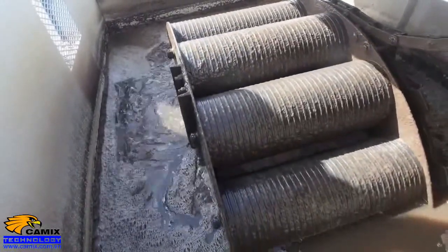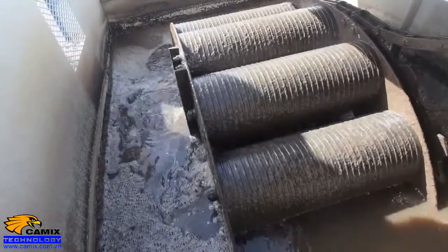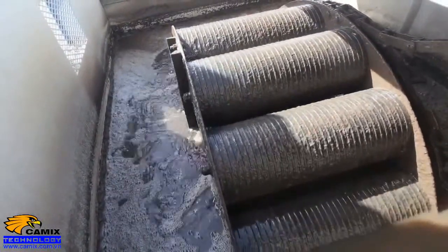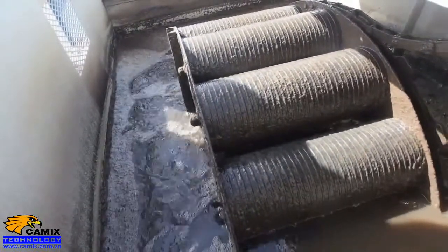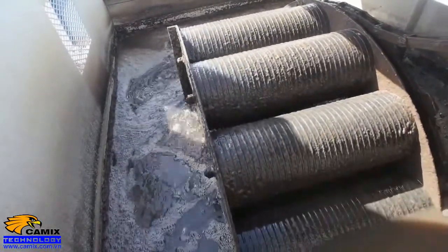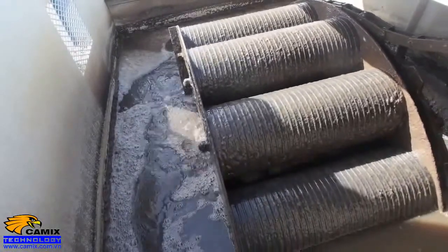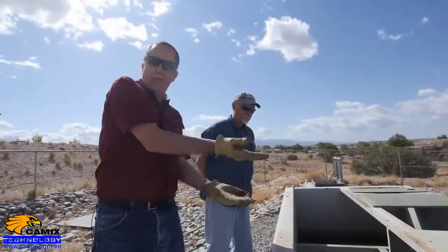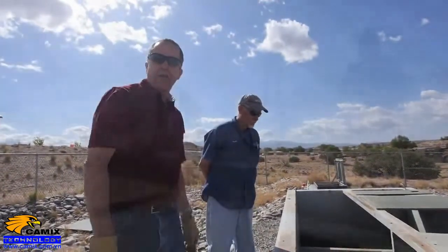And what's happening is as that rotor turns, it picks up the mixed liquor, and as it slowly rotates, when it gets above water, it spills that mixed liquor out and it aerates this top section. And then when the drums empty, they're full of air, they're full of oxygen, and then they submerge again on this end. They take that oxygen back down to the bottom of the tank and they slowly bubble that oxygen up through the mixed liquor.